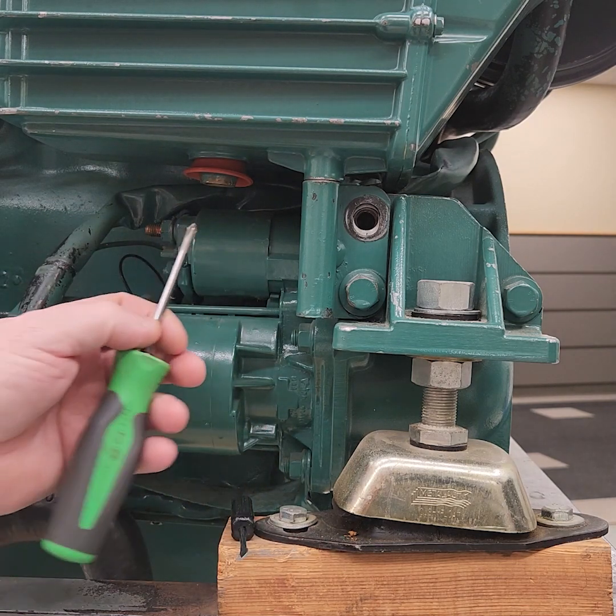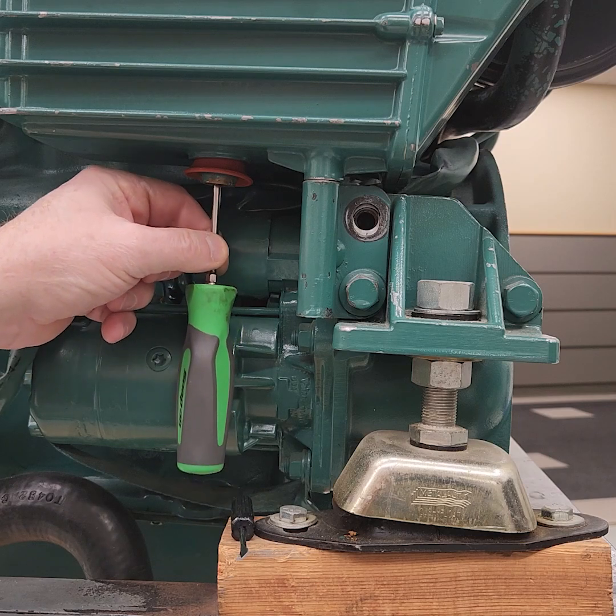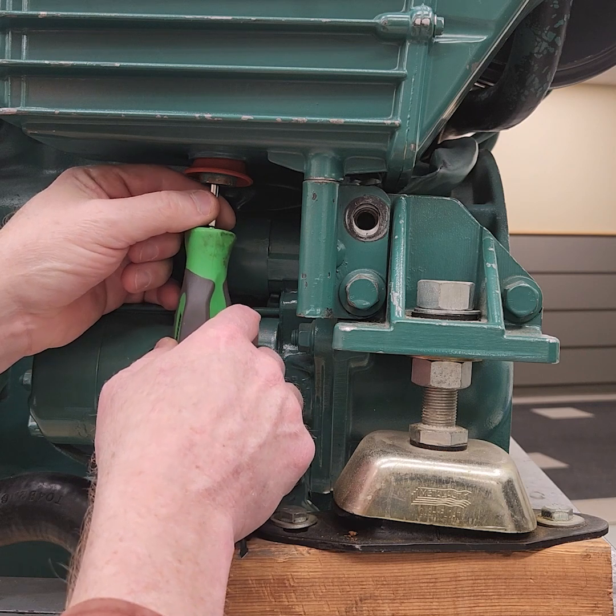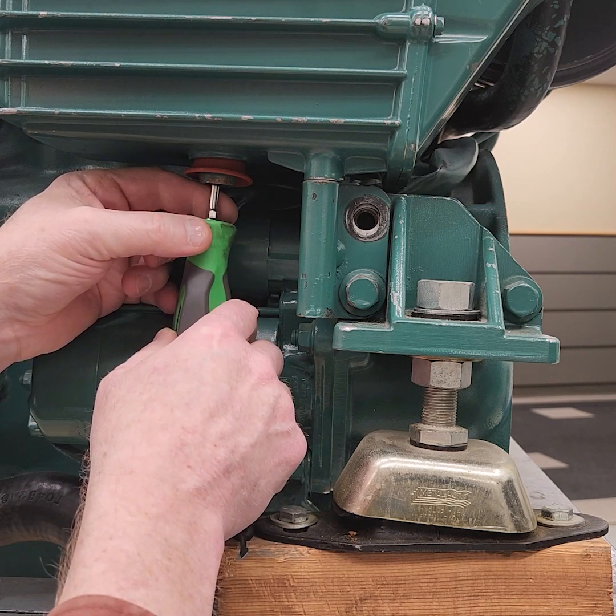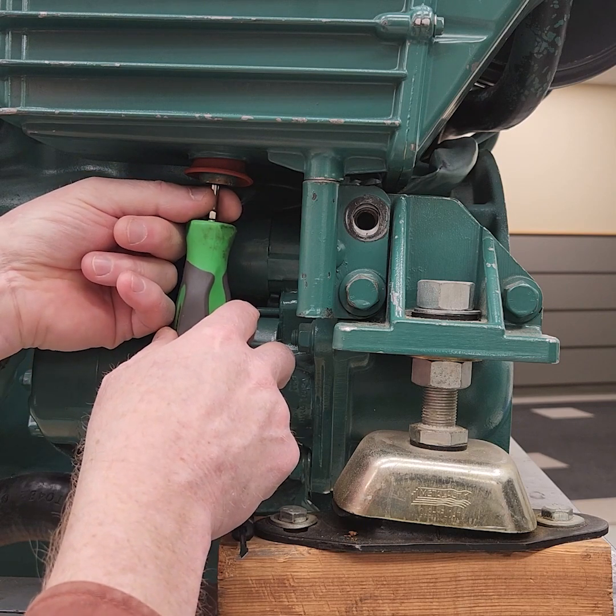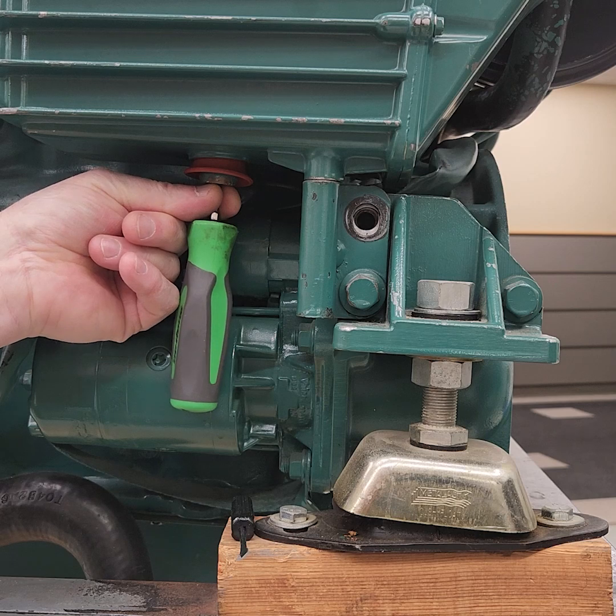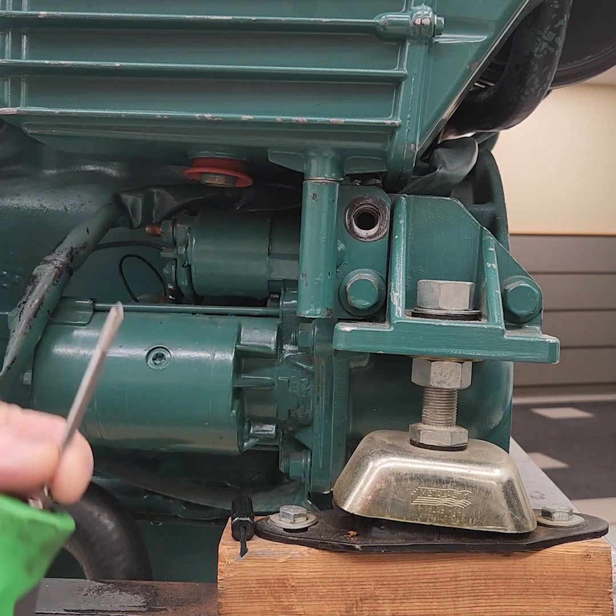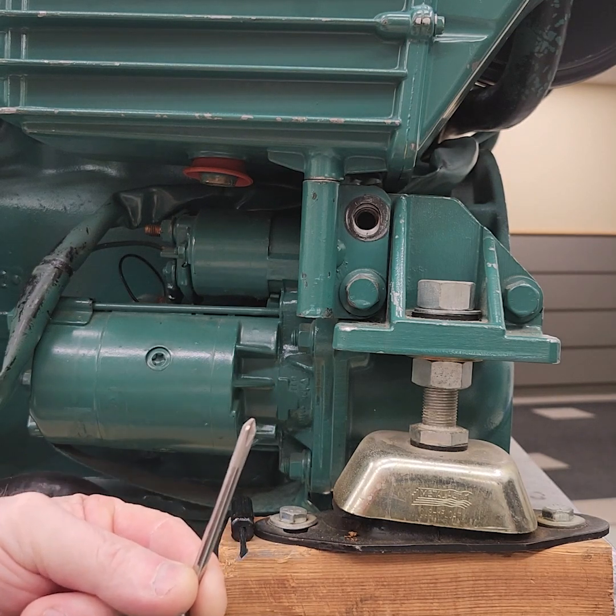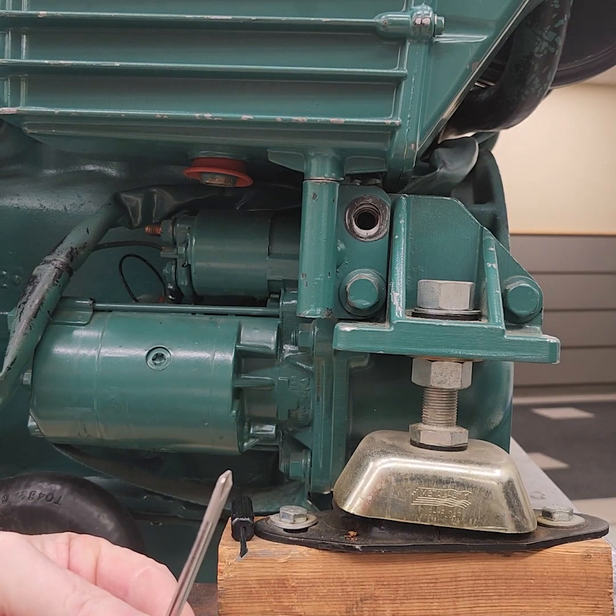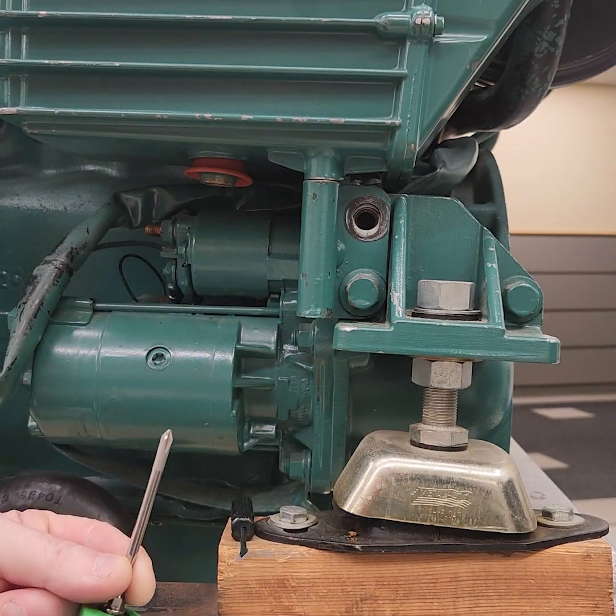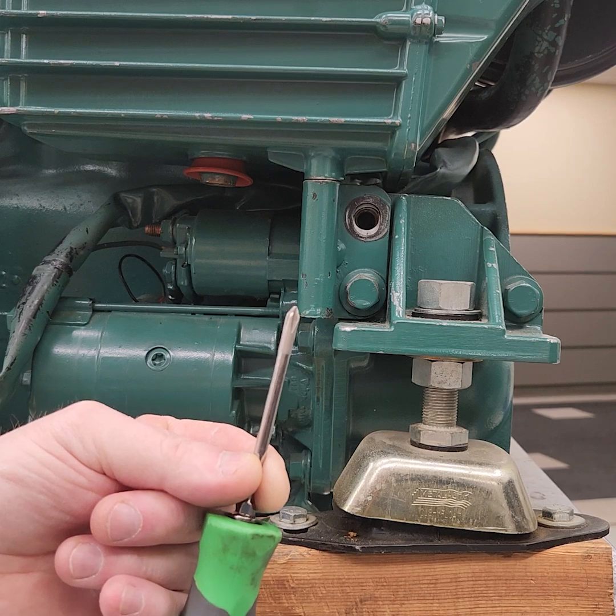Now, I want to know how far up those cooler tubes are. So if I come up with a screwdriver really lightly, and wiggle it back and forth until I feel it hits something, that's the cooler tubes right there. So you can hear that scratching off of it. So I'm going to hold it onto the cooler tube where it touches it, and I'm going to hold the screwdriver, and I'm going to pull it out. Now I'm going to take it over to the bench, and I'm going to measure this dimension, and obviously my anode has to be a lot shorter than that. I don't want it to be the full length, because if the anode's too tall, it will smash the tubes in and ruin the heat exchanger. So I'm going to go measure that and write it down.